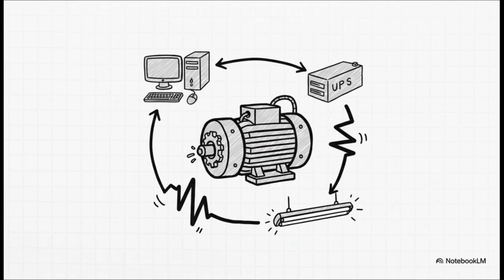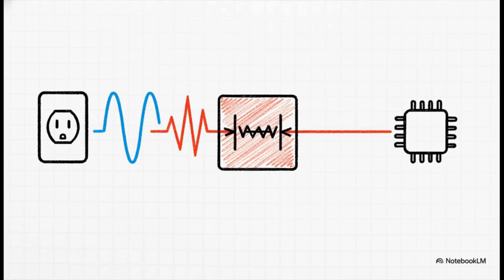So where is all this distortion coming from? It's generated by stuff we call non-linear loads, and that includes almost everything modern. From the big variable speed drives in factories, to the computers and UPS systems in your office, and even the ballasts inside fluorescent lights. But the number one culprit? It's the simple rectifier circuit.